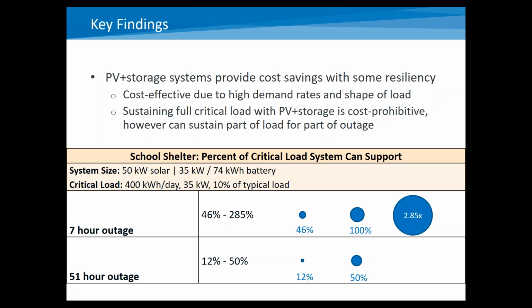So the recommended system size, if you're looking at maximizing economic savings and not imposing a resiliency requirement, meaning you don't have to sustain a certain number of hours of an outage, was 50 kW of solar, 35 kW, 74 kilowatt hour battery, and this supported a range of outages. If you're looking at a short duration outage, 7 hours, you could support around half of your critical loads under a worst case scenario, and about 2.85 times your full critical load under best case scenario. And that shrinks, of course, if you move to a 51 hour outage, about 2 days.